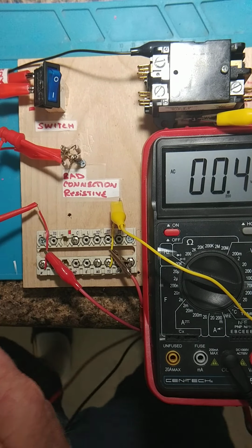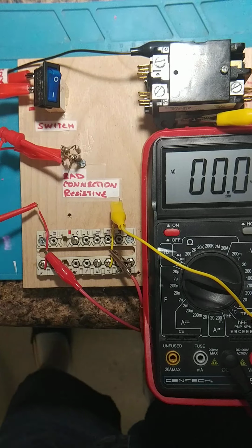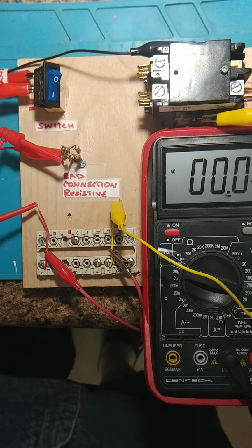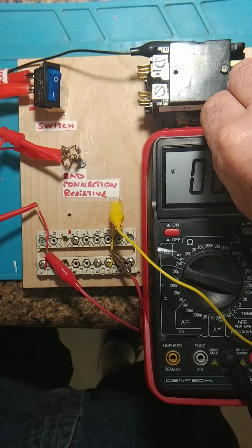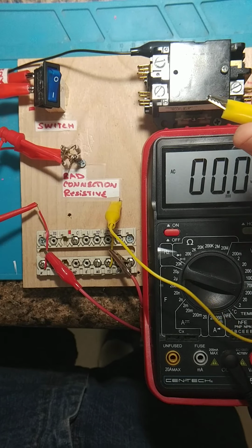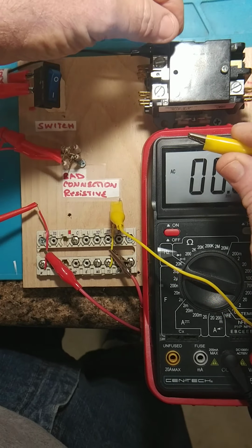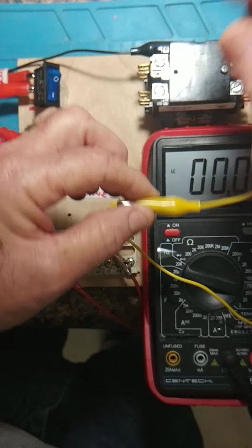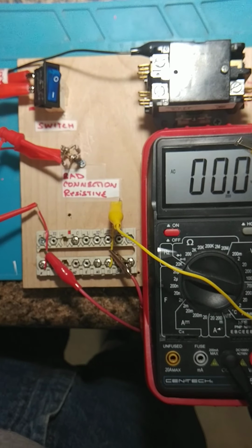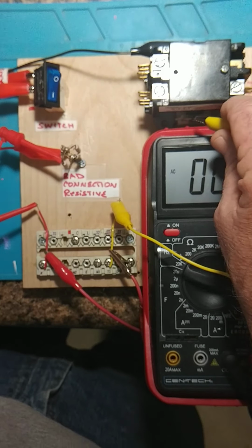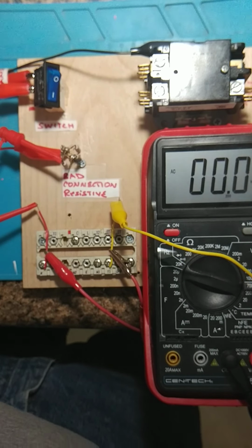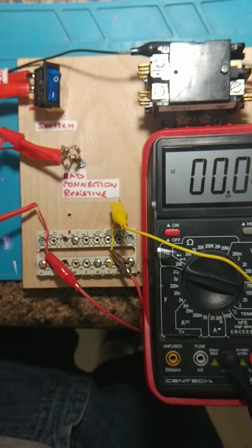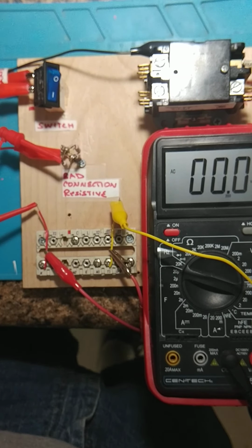And this is where resistive connections can be very, very difficult to troubleshoot and isolate. You can usually tell that's what you've got if you pull one of the wires off the coil of the relay or contactor, and if you've got 24 volts between the wire and that with it pulled off, and then when you reattach it, you've got much less voltage. That's telling you somewhere in your 24 volt wiring, you've got a really bad connection.